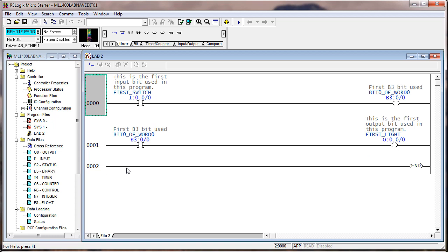So what I was demonstrating here was, you got to be careful what you're grabbing and dragging. If it is a rung that is running, you can grab a copy and drag it someplace else. If it is a rung online in the edit mode and you grab it, you're moving it. Offline, you can do anything you want.